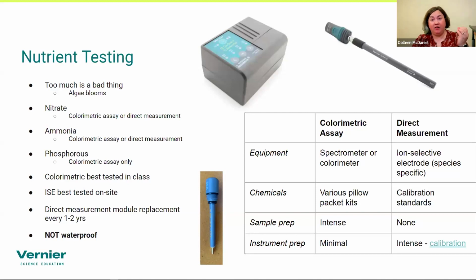Sample prep is very intense. There is the issue of chemicals, and in some cases, these can be some very hazardous chemicals that do need to be disposed of properly. A direct measurement method is using our ISEs, or ion selective electrodes. And these are going to be what we call species specific. So we have a very specific electrode that is just for nitrates. We have one specifically for ammonium ions and a few others for other chemistry purposes. Nitrates and ammonium ions are the ones we concentrate most on with water quality.